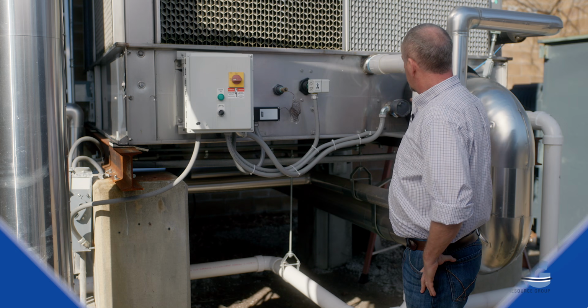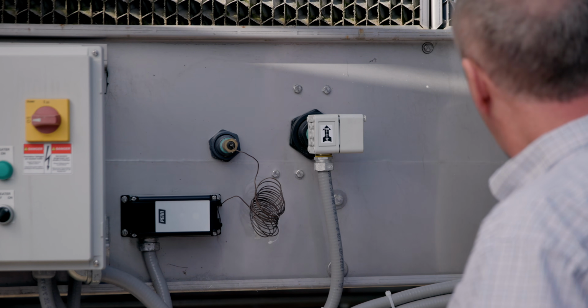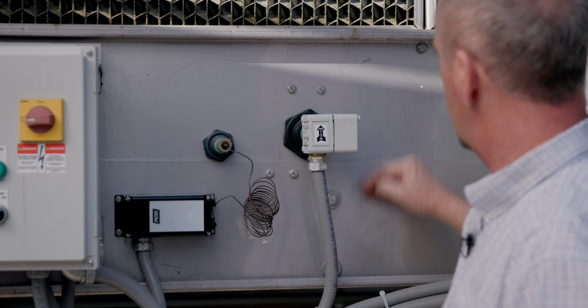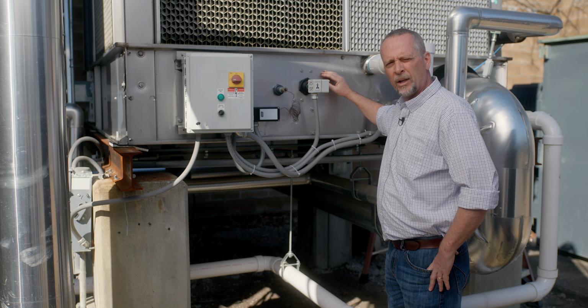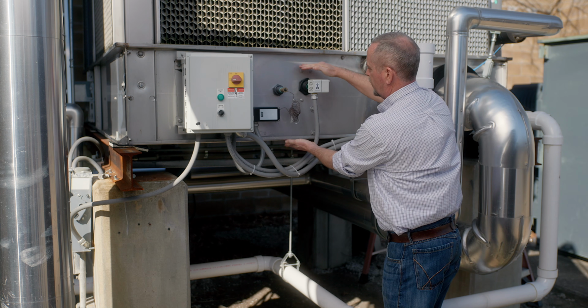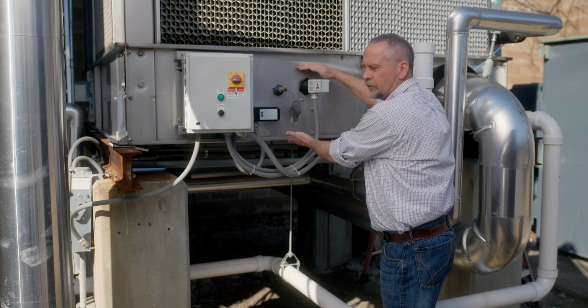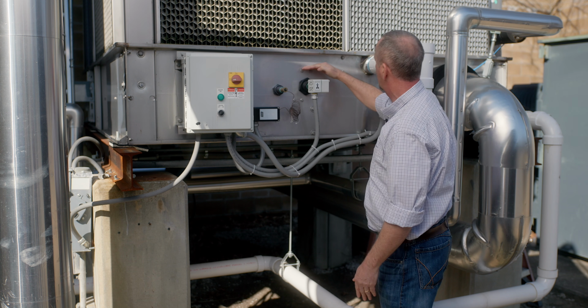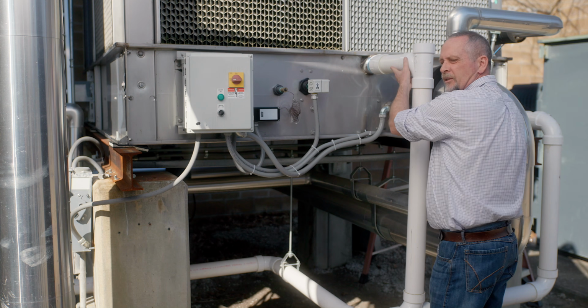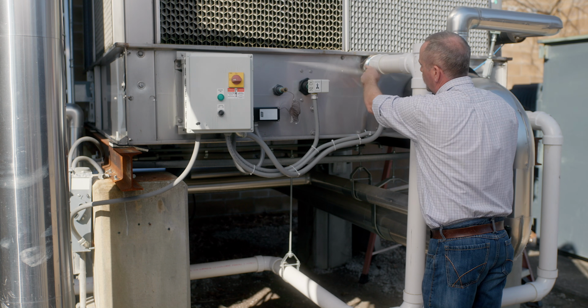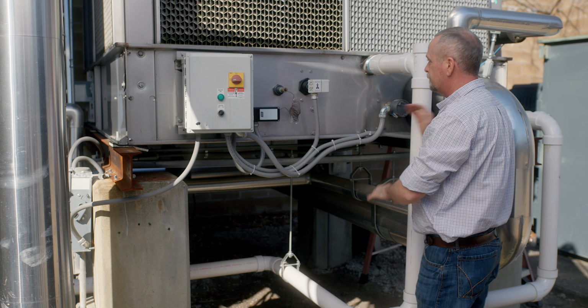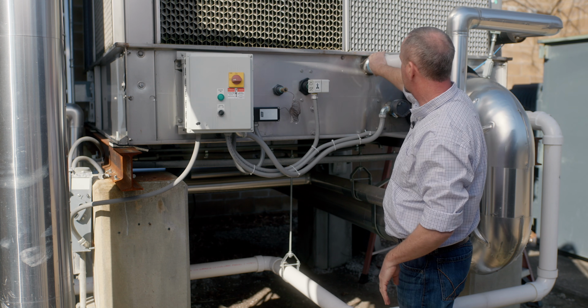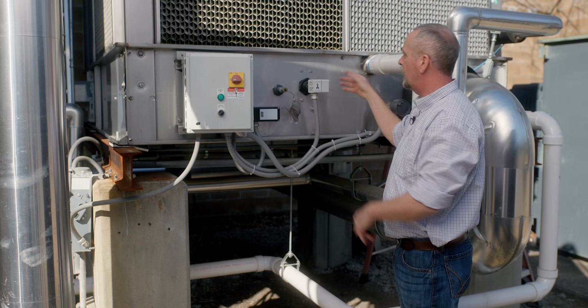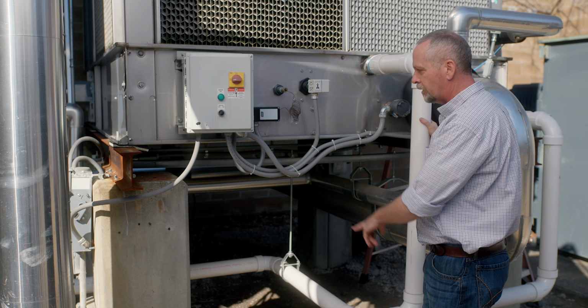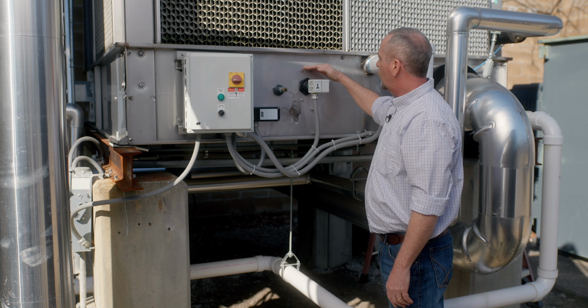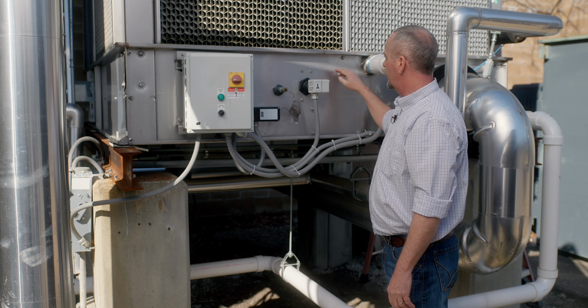Now, as we talk about this basin heater, the basin heater's purpose in this application is right behind me here, what we call the tower sump or the cold water basin. This portion of the tower is always full of water when the tower's in operation, about up to this water level. If you see this pipe, this is my overflow pipe. If my water level gets too high, it'll overflow and go out the drain. So you don't want it that high, but that's what that device is for, in case you're overflowing your tower, so it's not spilling out of the side of the tower and goes down the drain. So here's our water level mark, roughly somewhere right below that.